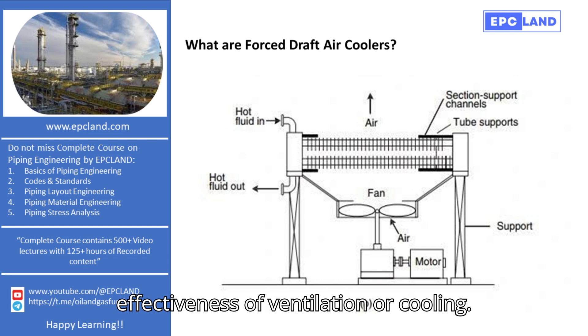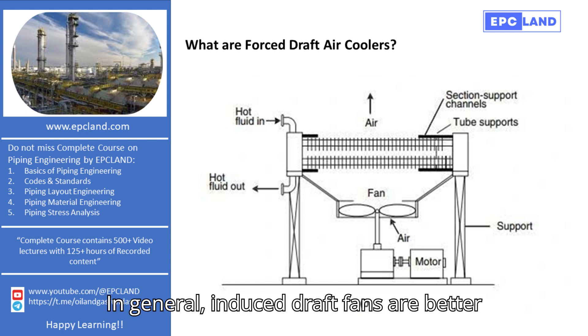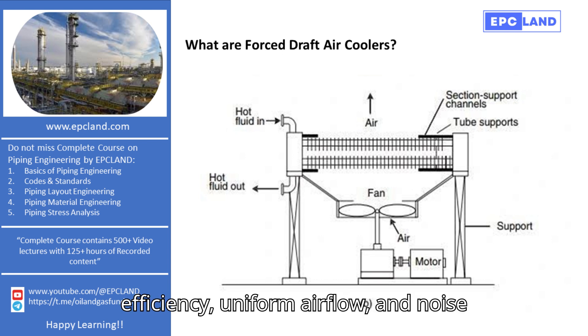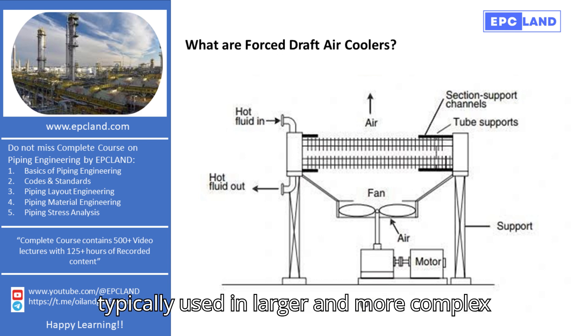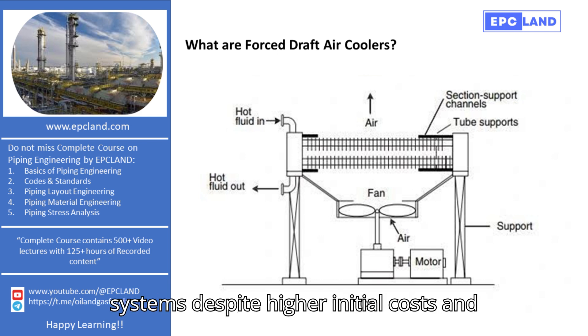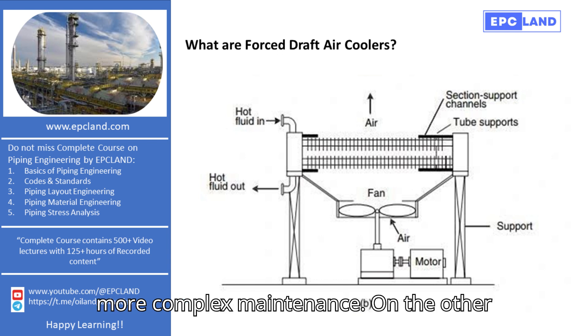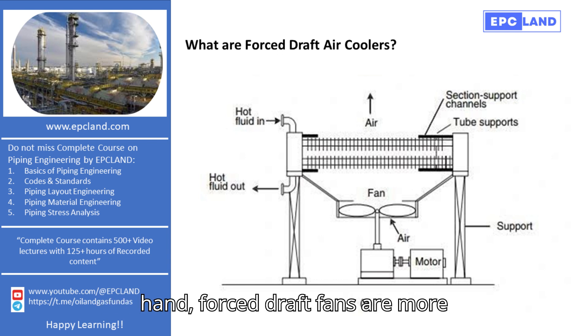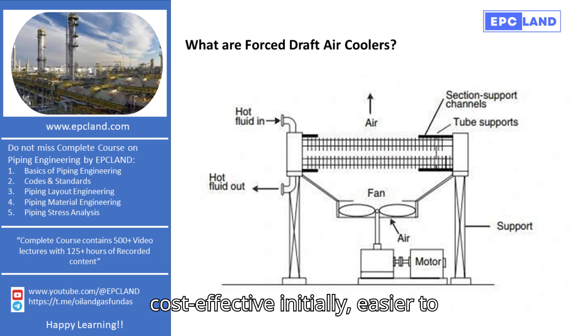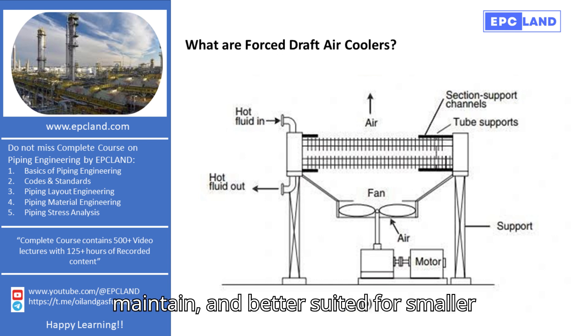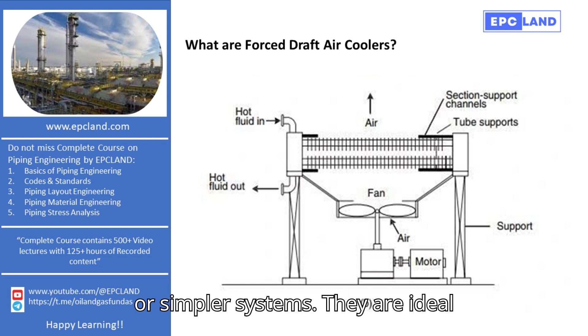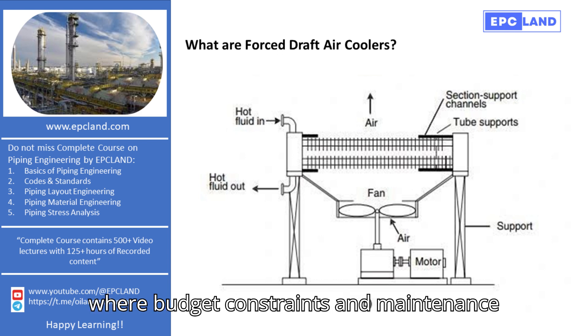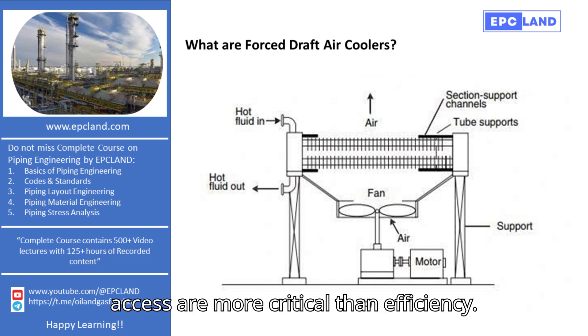In general, induced draft fans are better for applications requiring high efficiency, uniform airflow, and noise reduction at ground level. They are typically used in larger and more complex systems despite higher initial costs and more complex maintenance. On the other hand, forced draft fans are more cost-effective initially, easier to maintain, and better suited for smaller or simpler systems. They are ideal where budget constraints and maintenance access are more critical than efficiency.